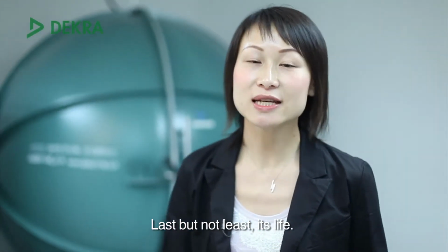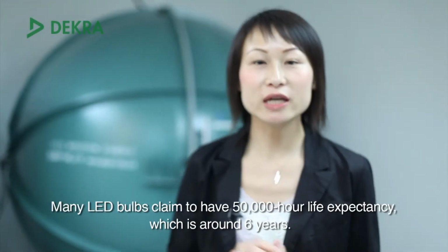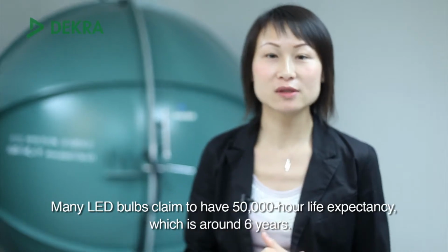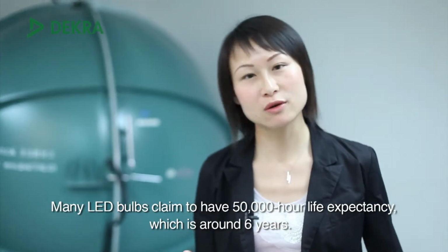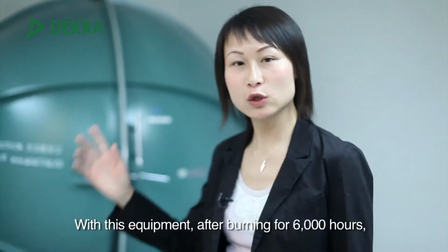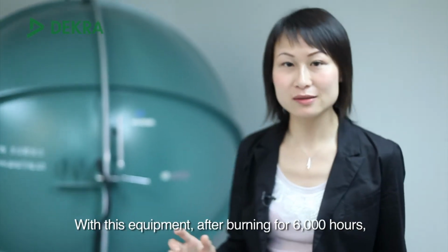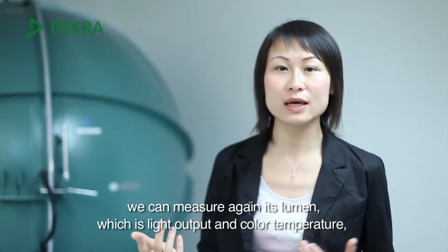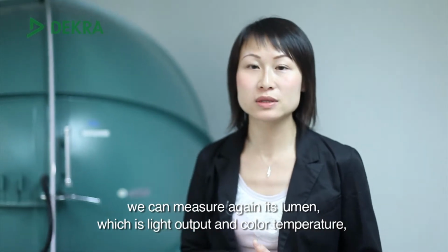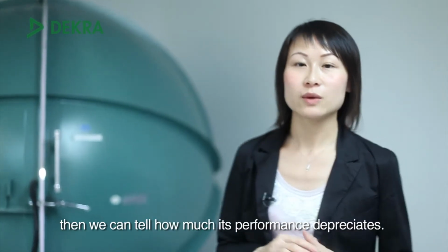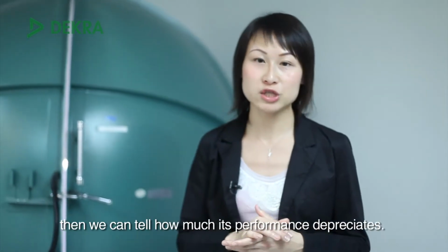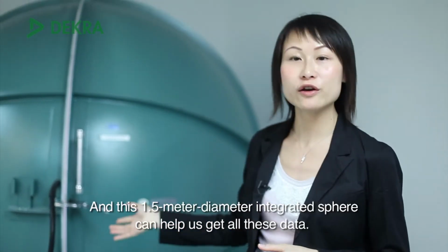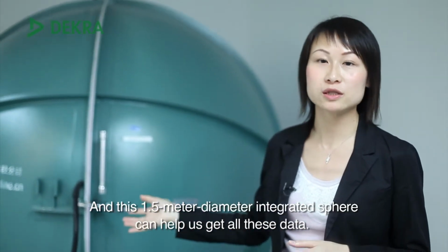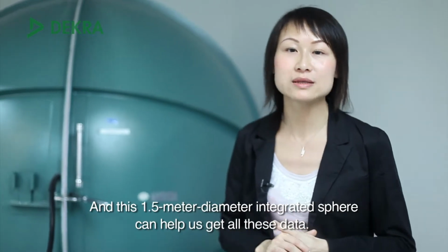Last but not least, its life. Many LED bulbs claim to have 50,000 hour life expectancy, which is around 6 years. With this equipment, after burning it for 6,000 hours, we can measure again its lumen, which is light output, and the color temperature. Then we can tell how much its performance depreciates. And this is the 1.5 meter diameter integrated sphere that can help us get all these data.